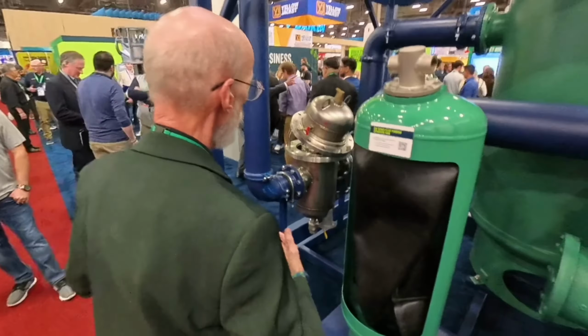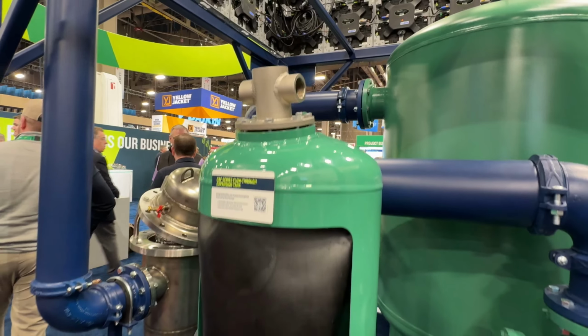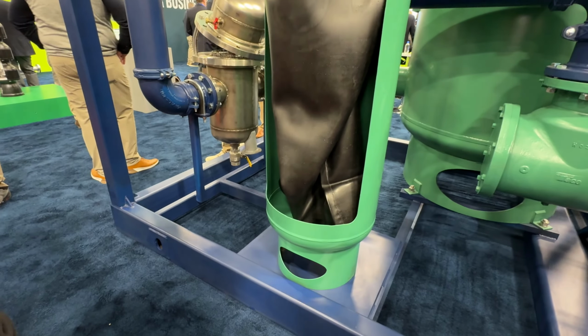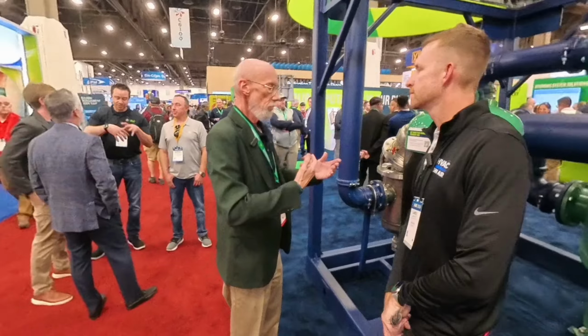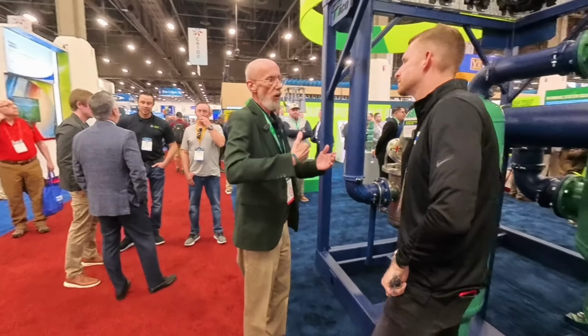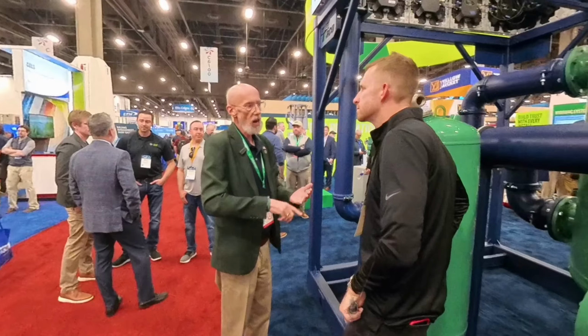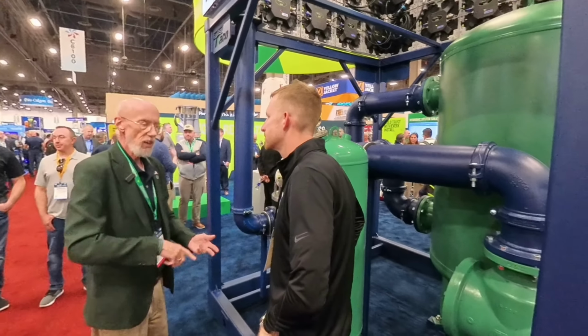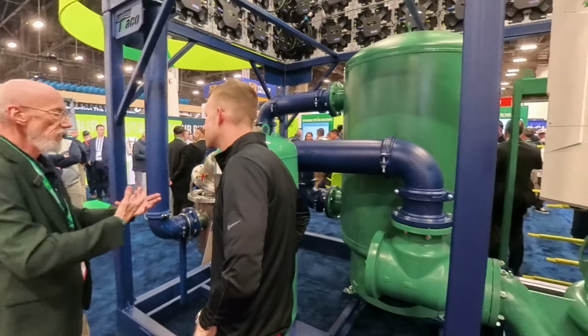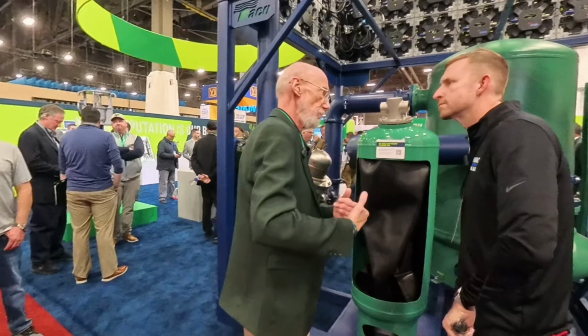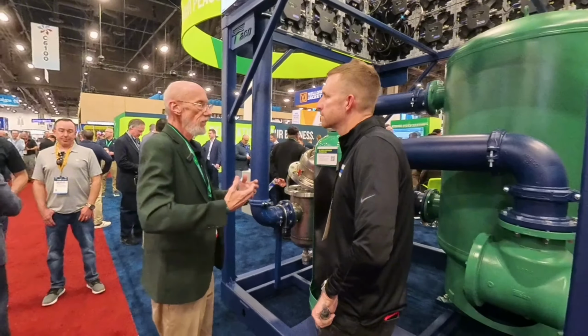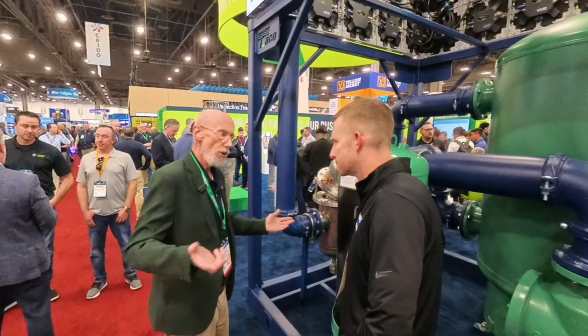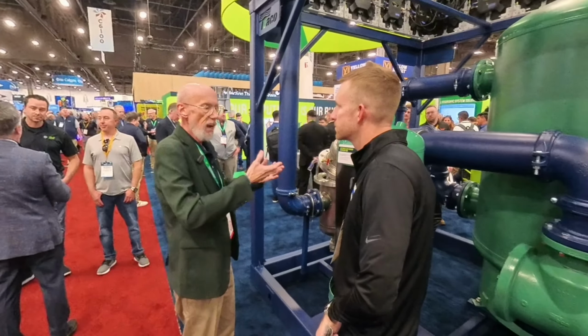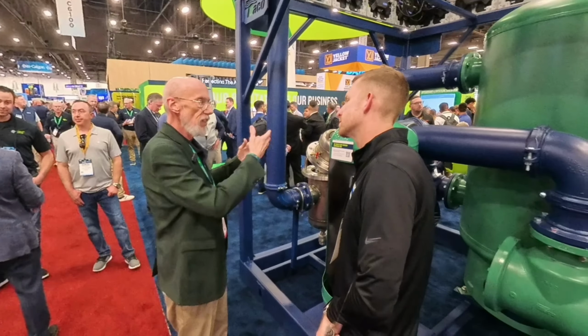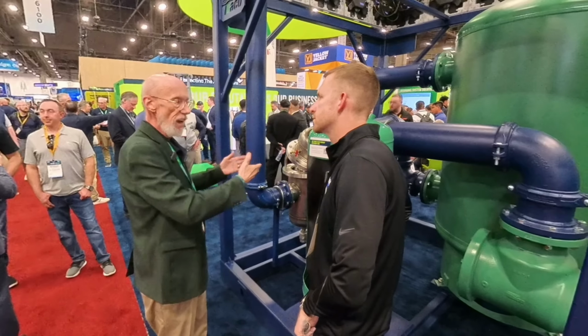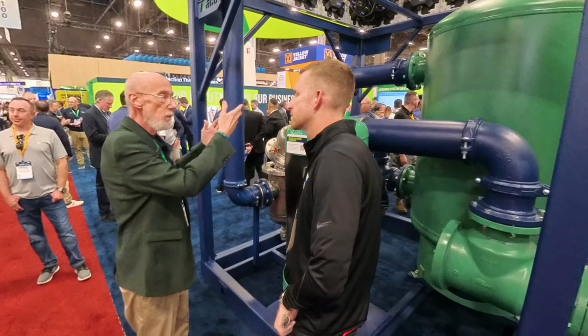So, we also supply product for the plumbing industry. One of the challenges we have in the plumbing industry is Legionella. Plumbing code requires that in healthcare facilities, and healthcare facilities are hospitals, nursing homes, inpatient hospice care, things like that, they have to have what's known as a water management plan. Part of that water management plan means that they can't have any dead legs or stagnant water anywhere in their system. Well, on a domestic hot water system, there's one thing that's a point of stagnant water, and that's the expansion tank.